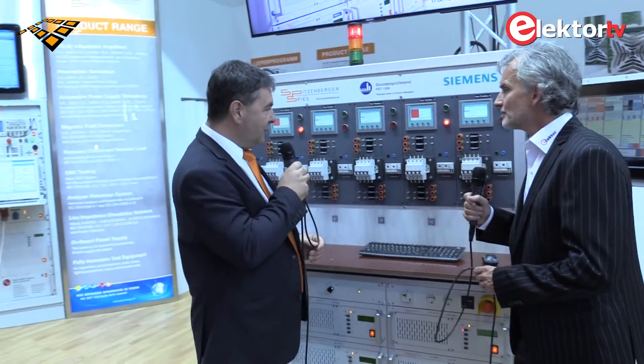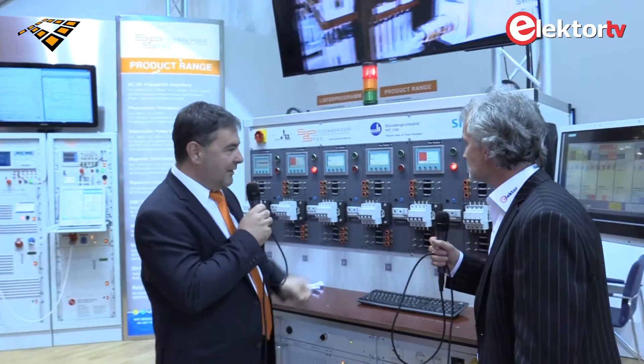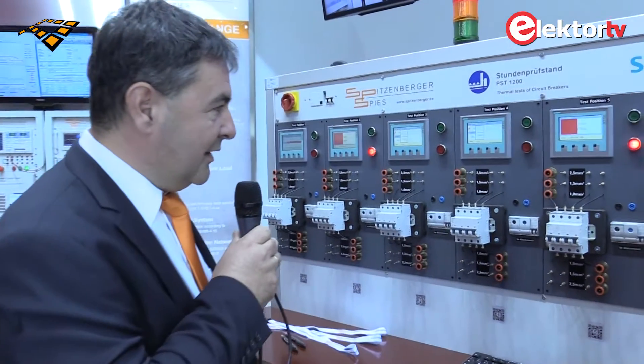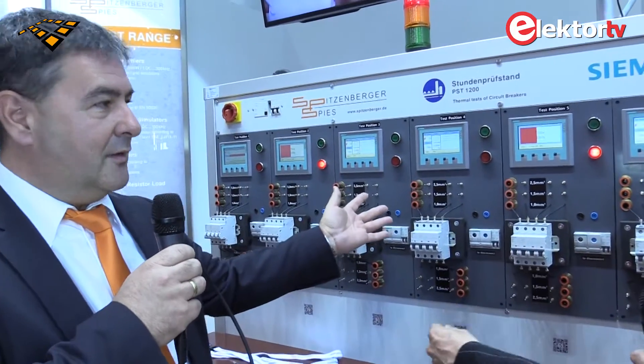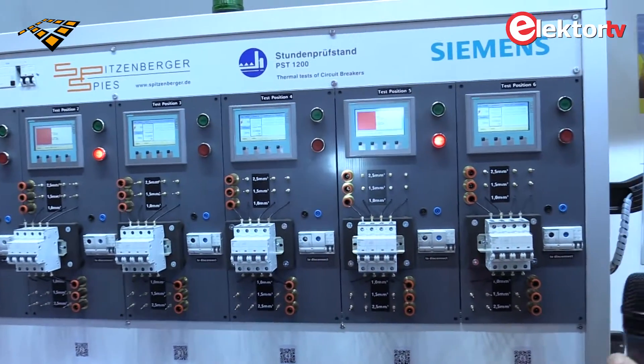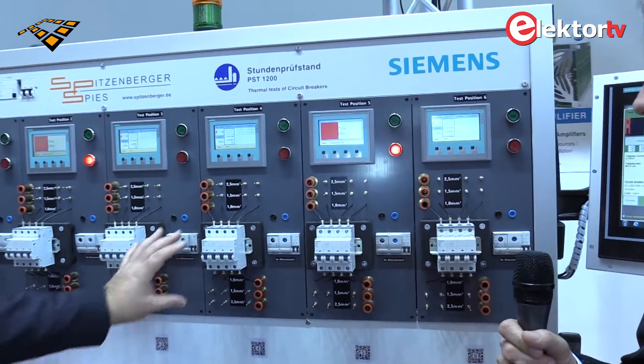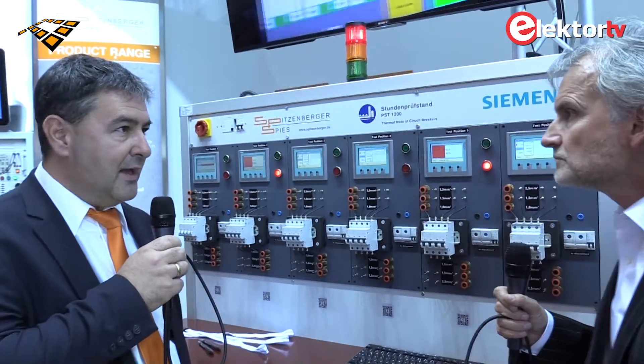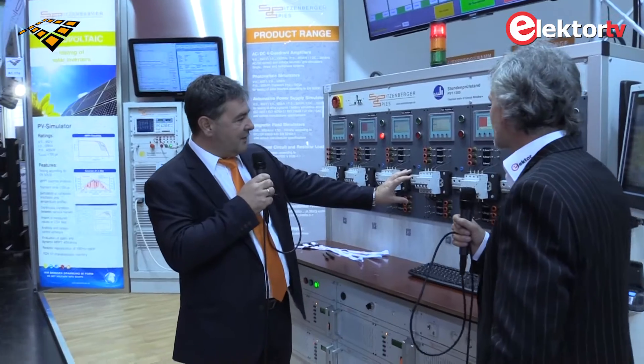Both possibilities are available at this test bench. We have this household appliance unit, with household appliance units up to 2.5 mm² in diameter. This can drive up to 75 amps. And we have a similar test bench for higher currents, for industrial appliances up to 125 or 200 amps. What we are testing here is the characteristic of these safety units.